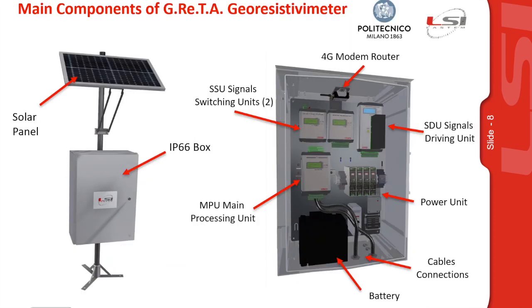In this slide, the main components of the system are explained. The device is inside one box — in this picture with a solar panel, though the system can also be connected to the power grid. Inside the box, there are different components: the signal switching unit, the signal driving unit, the main processing unit, the power unit and battery, and the communication part with a 4G modem or router. The picture also shows the connections to the cables that will be connected to the electrodes.